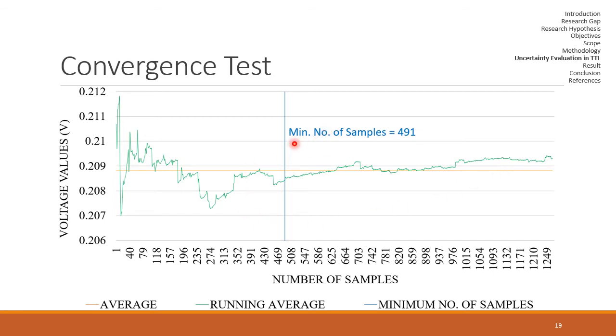So minimum number of sample is the number of samples required to meet the IEC standard. That is, it is the number of sample required to get the uncertainty less than or equal to 0.2%. So for this fourth loading at number of samples 491, not only we get the uncertainty value 0.2%, but after this point all these uncertainty values are less than 0.2%. So that is quite amazing.